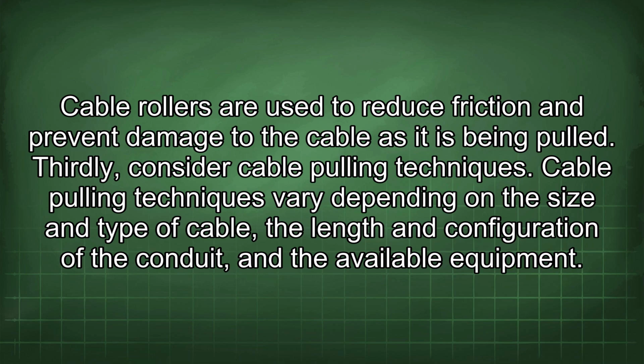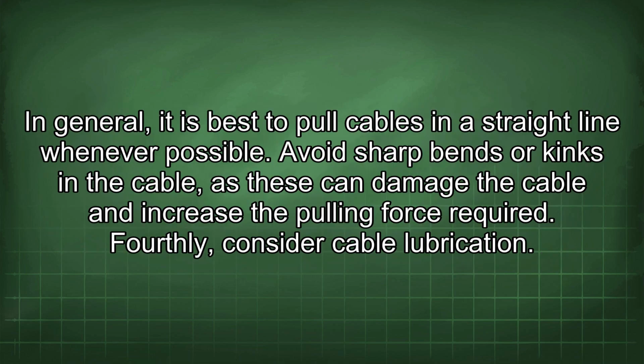Thirdly, consider cable pulling techniques. Cable pulling techniques vary depending on the size and type of cable, the length and configuration of the conduit, and the available equipment. In general, it is best to pull cables in a straight line whenever possible. Avoid sharp bends or kinks in the cable, as these can damage the cable and increase the pulling force required.